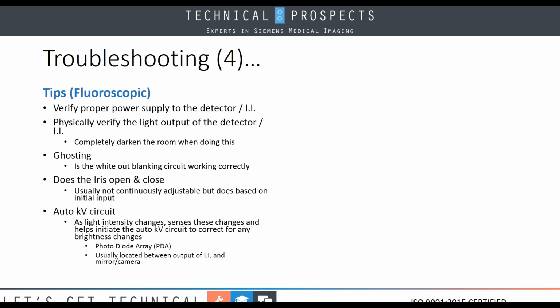Looking at some tips for fluoroscopic. All right, we talked about it earlier. Check the power supply voltage of the detectors and the IIs. If these are correct, that's the important thing in terms of making sure that these devices are working correctly. If you can physically verify the light output of the detector or our II, that's great. Little tip when you do this though, completely darken your room. All right, because otherwise you're going to be affecting other parts of the circuit when you remove the cover, because you don't want to expose it to all the white light.